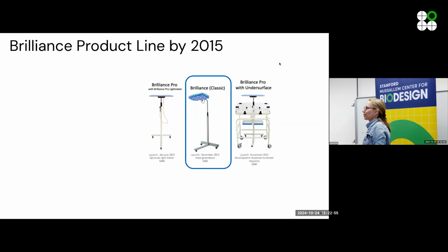You really learn about what's wrong with your product after it launches. Those of you who have designed medical devices know this already, but to give you a sense, one of the big errors we made was that you needed 2 hands to lower the head. Phototherapy devices need to scope up and down, but you needed 2 hands to do that. And remember I mentioned these really busy nurses? You really need to be able to do that with 1 hand. Another thing we didn't do very well is the readout. You have to get right up to read it, and of course, if you're really busy, you want to be able to read it across the room.